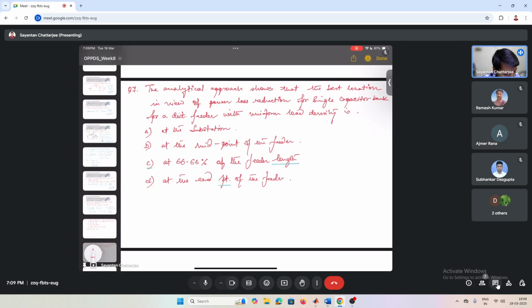The analytical approach shows that the best location, in view of power loss reduction, for a single capacitor bank for a distribution feeder with uniform load density is: at the substation side, at the midpoint of the feeder, at 66.66% of the feeder length, or at the end point of the feeder.